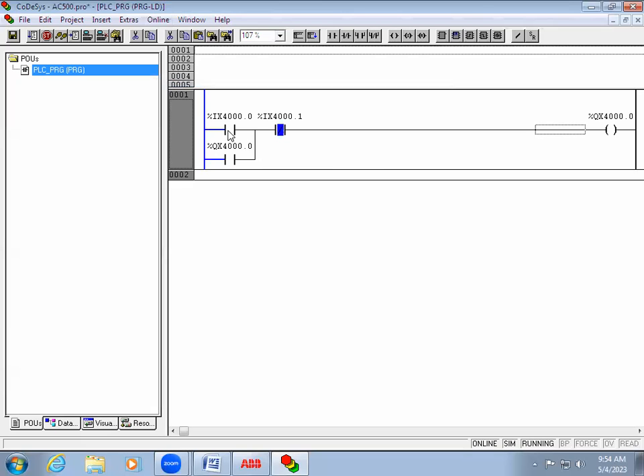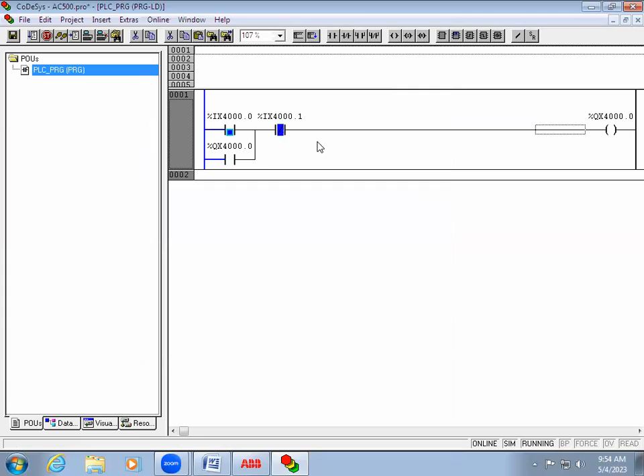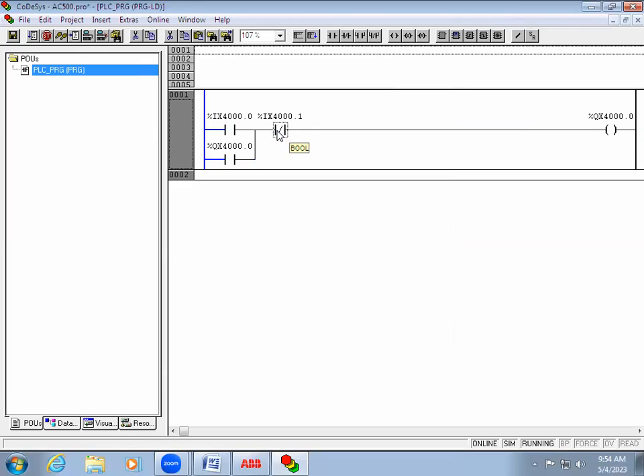To turn on an input, double-click it — it will show a dot — and in online mode we right-click to write values, or use the shortcut F7 to force it on. The output turns on. Now I'll turn the input off — due to the latch, the output remains on. When I activate the second input (the stop contact), the output turns off.